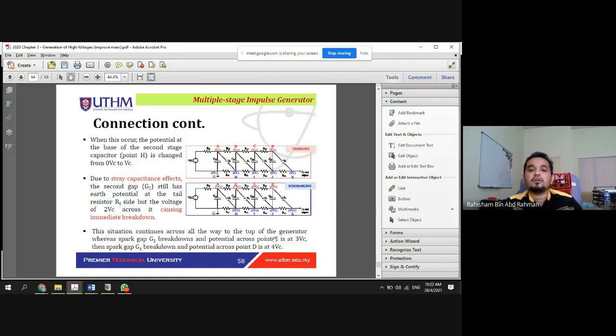What is 4VC? 4 times 100, 4 times the charging capacitor voltage. So this one is 100, this one 200, this one 300, this one 400. They are in series. 100 plus 100 plus 100 plus 100 gives us 400 at the output to the test object. That's why if we apply the test object at this point, we will have a 400 kV impulse.